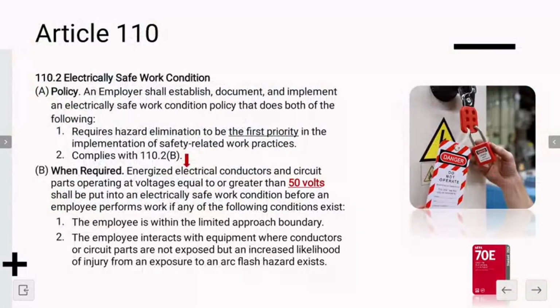Okay. The 70E also requires, and really get this in, burn this in your brain, that the employer's electrical safety program has to require hazard elimination to be the first step when we need to control an electrical hazard. How do you eliminate an electrical hazard? What? Yeah, turn it off. Turn it off and lock and tag it out, right? It's required in Article 110.2(A)(1) and (2).